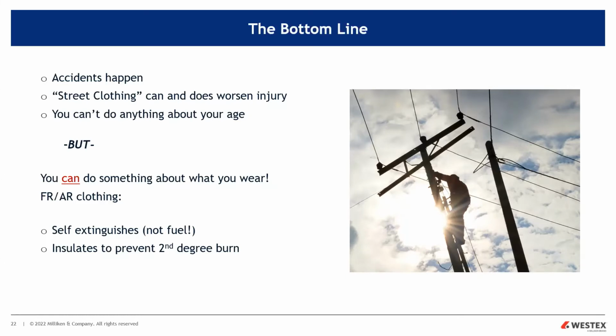And the term I like to use, a lot of people say it's just FR clothing. The term I like to use is FR arc-rated clothing or flame-resistant arc-rated clothing. Because there's 2 roles of flame-resistant arc-rated clothing. Job 1 is the FR, the flame resistance. It's got to self-extinguish. It's got to self-extinguish on day 1 and day 1001. The flame resistance can't wash out. It's got to be a quality fabric where it doesn't wash out because that's job 1. You can't wear fuel. The arc flash, as we all know, is 1/10 of a second. Well, we want to keep it that way. If you've got flammable clothing, you're wearing fuel, you extend the duration of the thermal exposure. It's like having your finger in a lighter for a long period of time.